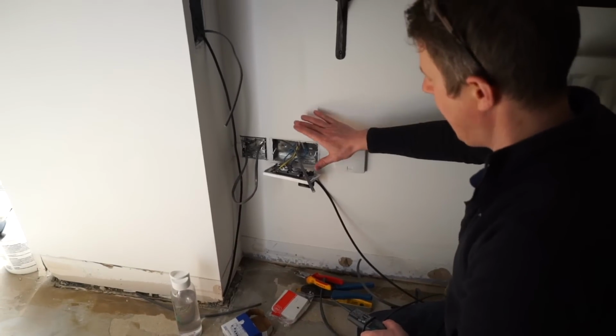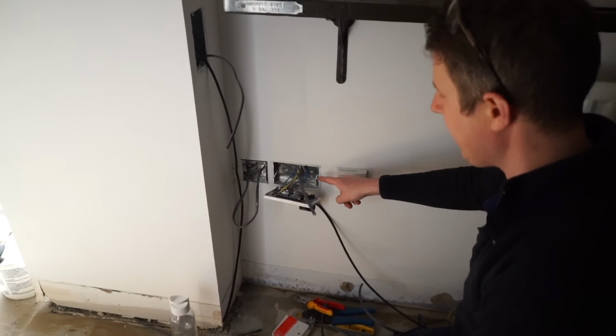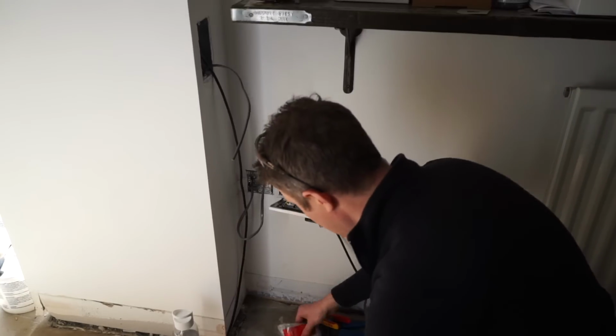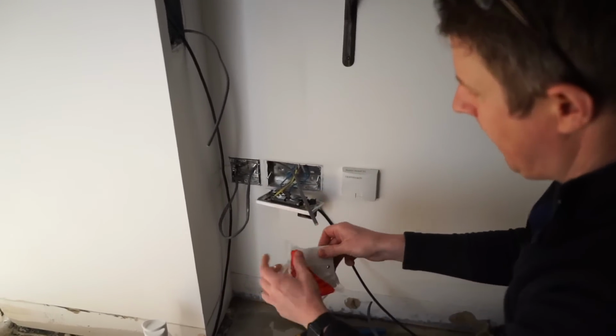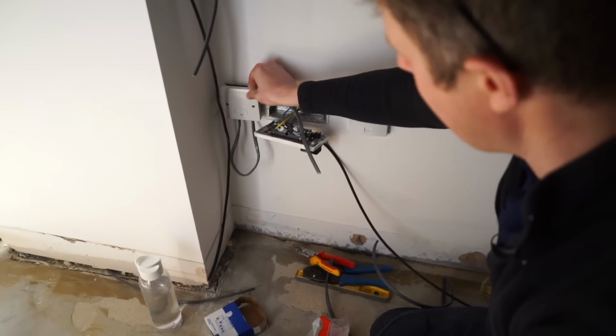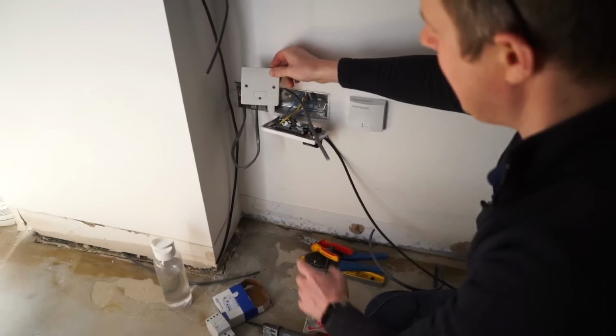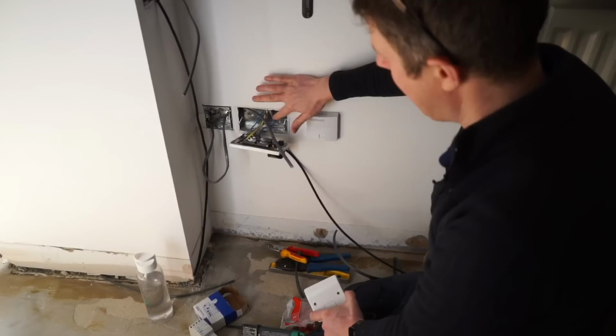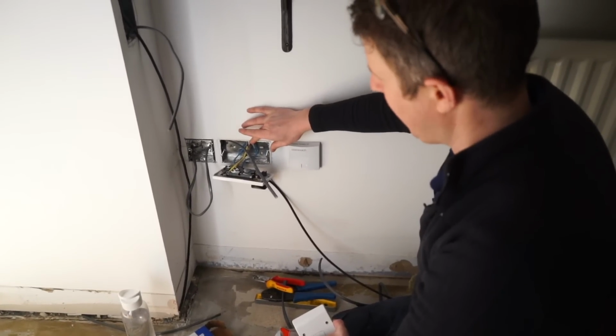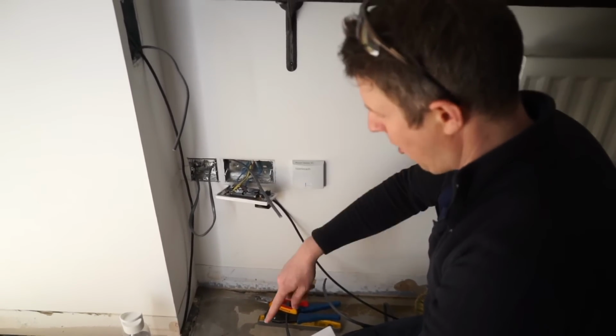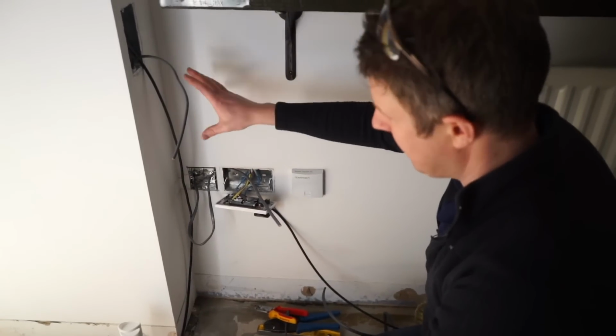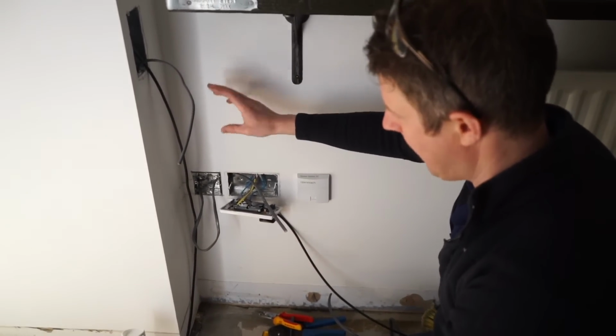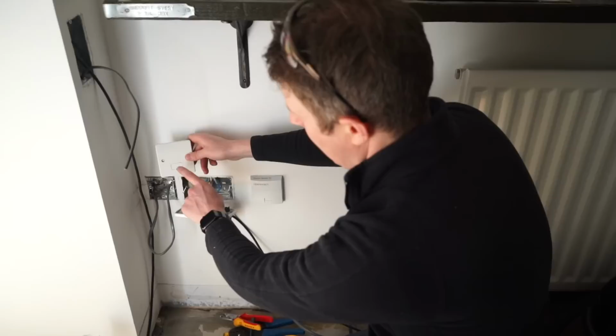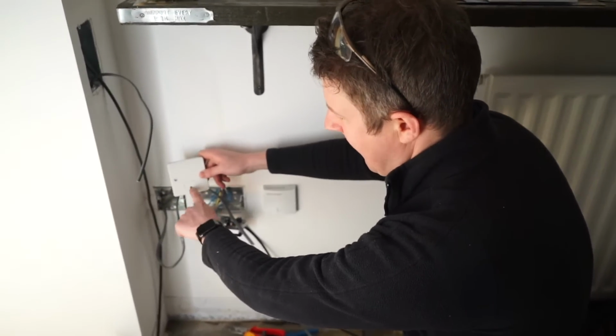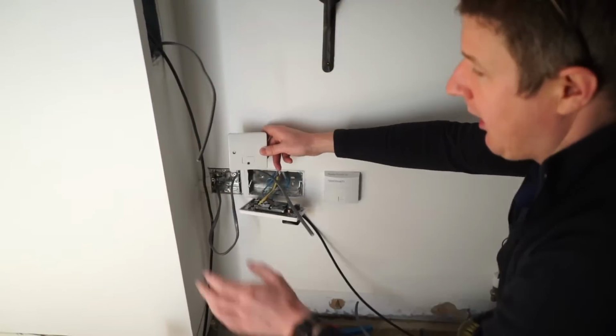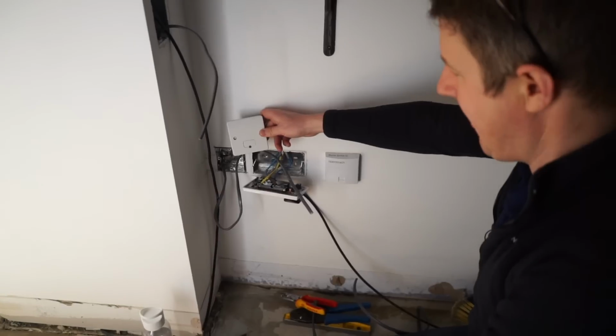So what we're going to be doing is taking our main power supply from this double socket into a fused connection unit, otherwise known as a fused spur, which goes here. The reason we put this in is because this circuit for the sockets is on a 32 amp circuit breaker, but the transformer and cables for the Nest Hello are rated a lot lower than 32 amps. So we put this in with a 3 amp fuse, which protects everything going out from it, so we know it's all safe.